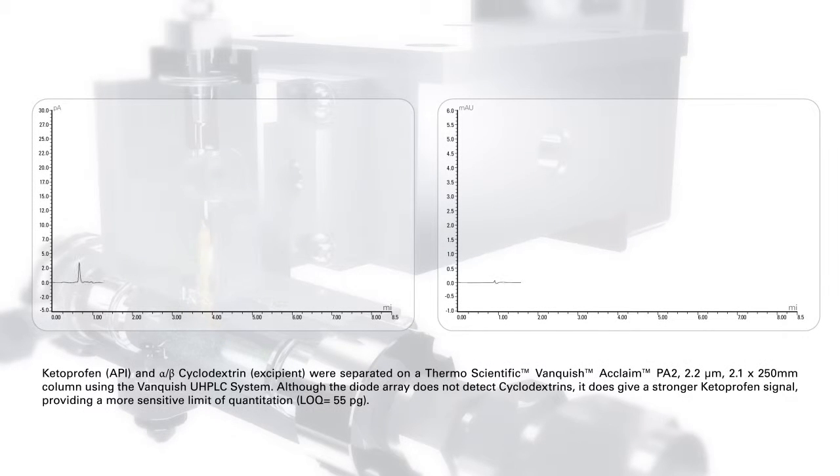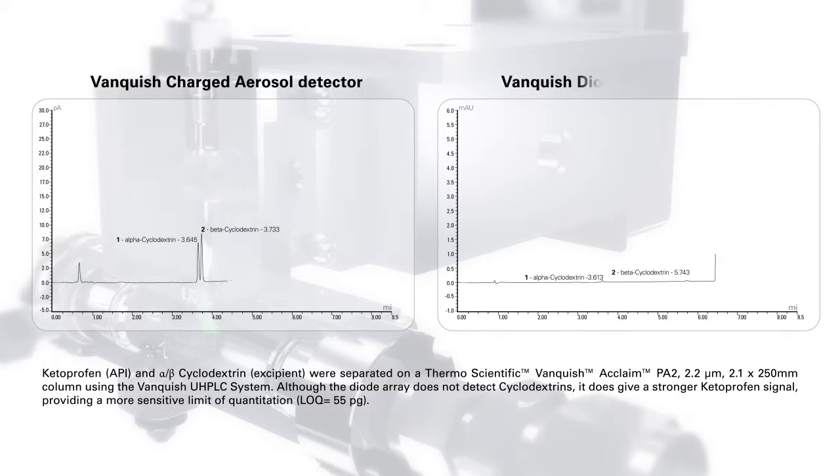These two chromatograms from a Vanquish system configured with both a charged aerosol and diode array detector show the separation of a drug delivery preparation of the non-steroidal anti-inflammatory drug ketoprofen that also contains cyclodextrin to improve solubility and bioavailability.